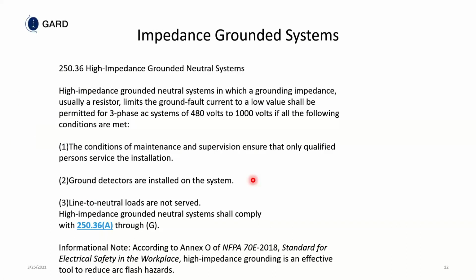So the NEC has a high impedance grounded neutral system. A high impedance grounded neutral system is one in which a ground impedance, usually a resistor, limits the ground fault current to a low value. Although the United States does not limit or define a low value, it is understood that 10 amps or less is a low value, provided that the service conditions of maintenance ensure that only qualified people service the installation, ground detectors are installed, and line to neutral loads are not served.